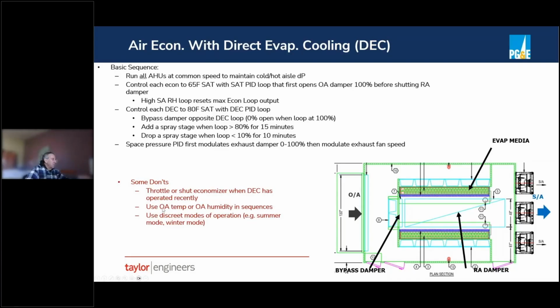You don't need to use the outside air temperature or the outside air humidity in the sequences. You don't really care what the outside air conditions are when you're doing direct evap. All you care about is what's being supplied into the space, because that's going to dictate how you control your dampers and control your media. So you don't even need to know the outside air temperature and humidity. All you need to know is what the supply air temperature is. And so again, it's a pretty simple system at the end of the day.